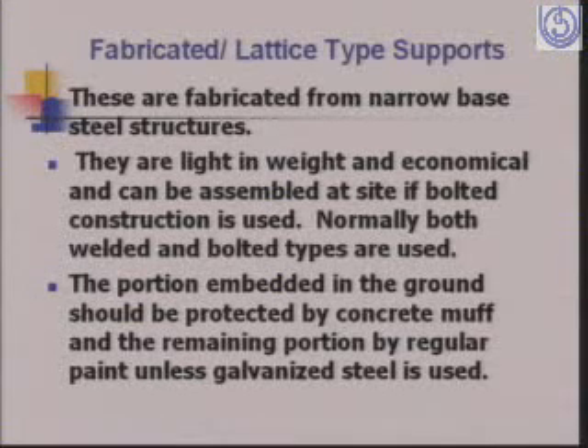Then we have the fabricated or lattice type supports. These are fabricated from narrow base steel structures. They are light in weight and can be assembled at site if bolted construction is used. Normally both welded and bolted types are used, and the portion embedded in the ground should be protected by concrete muff and the remaining portion by regular paint unless galvanized steel is used.